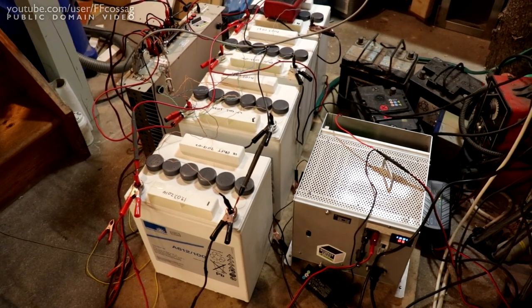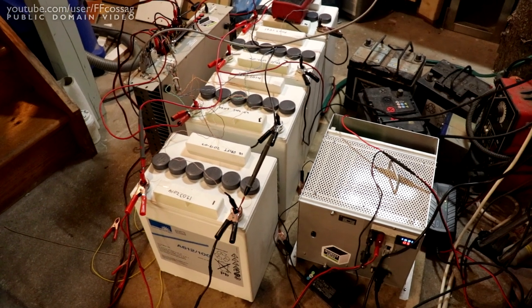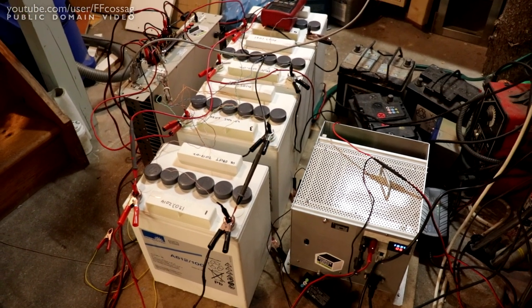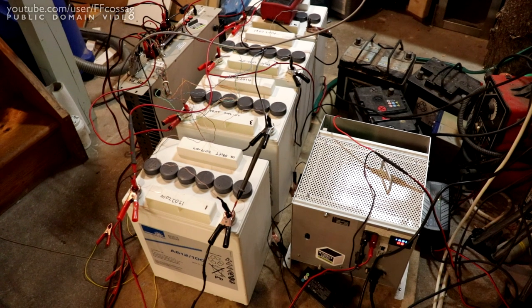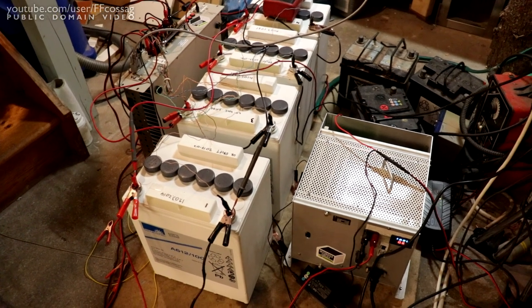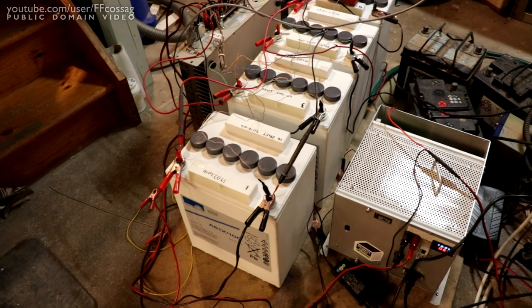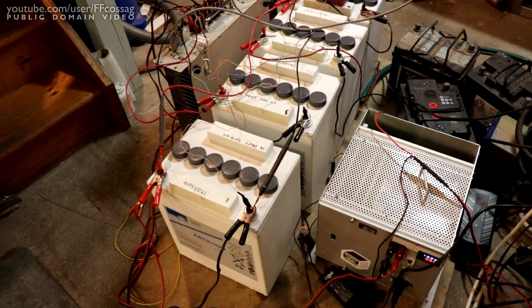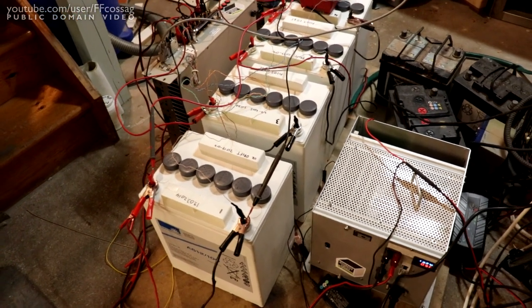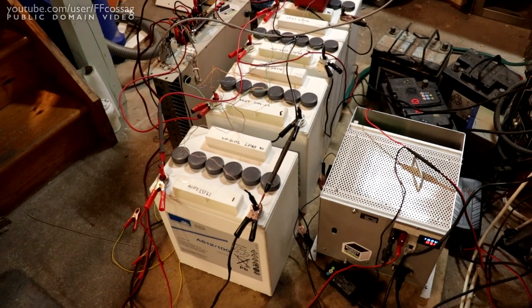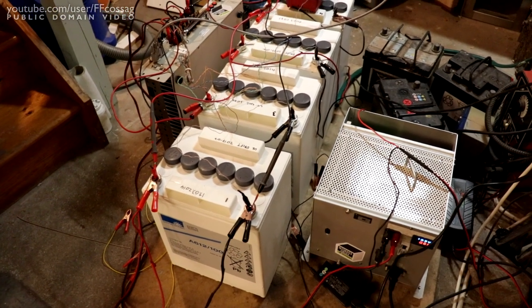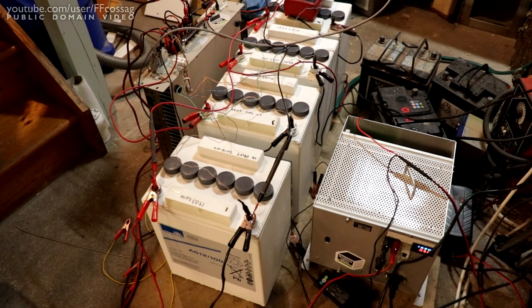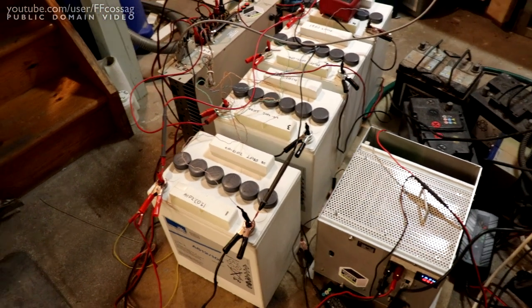The technician said it was, you know, not much below 12.6 per block, but there was probably at least one which was below 12.6, which isn't bad. Sonnenschein gel blocks, they tend to take cold storage without a charger really, really well. And even if they sit around half charge for a while, they tend to make it out quite well.